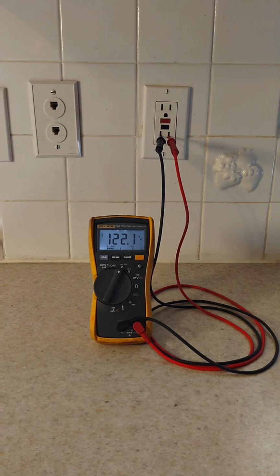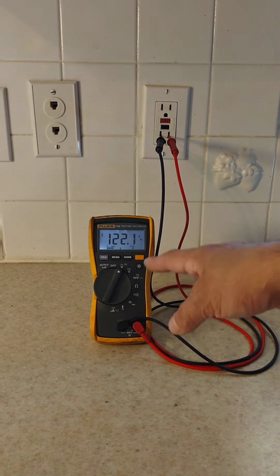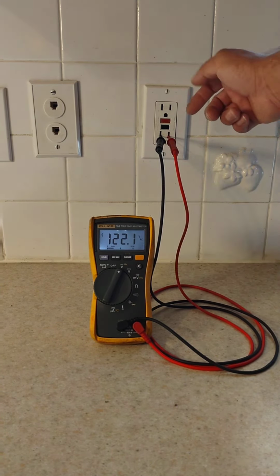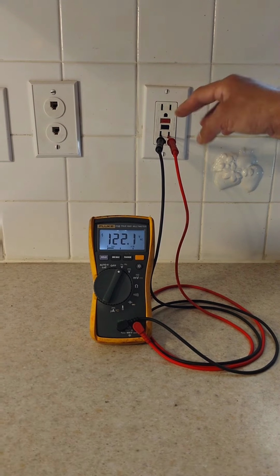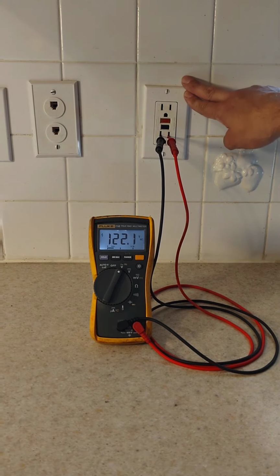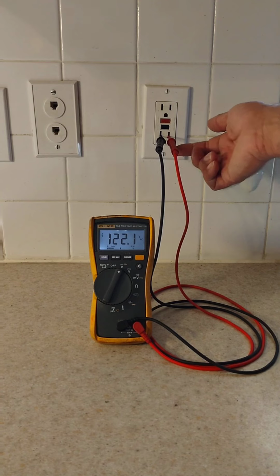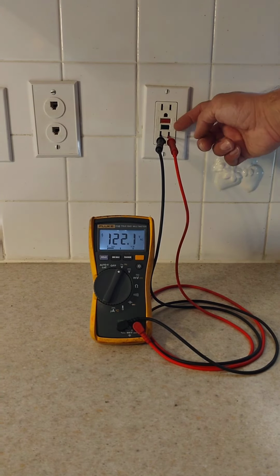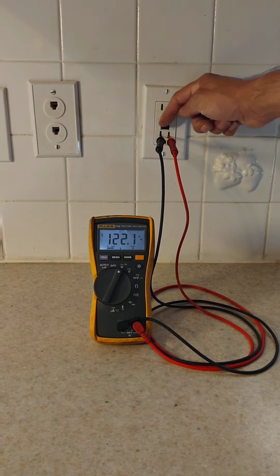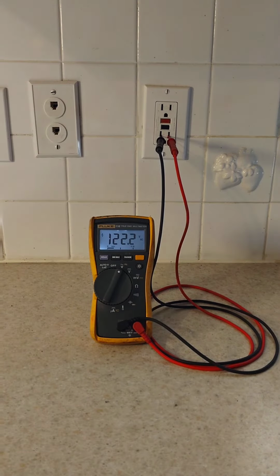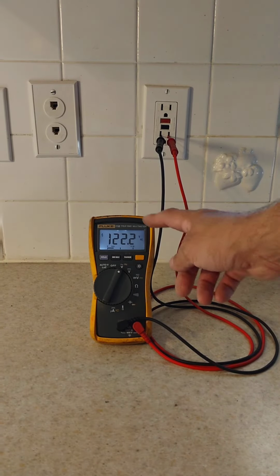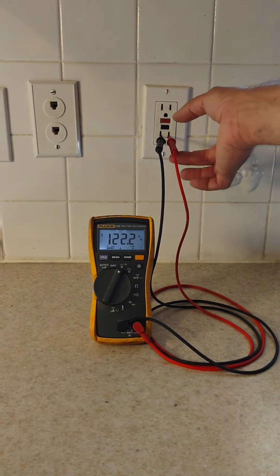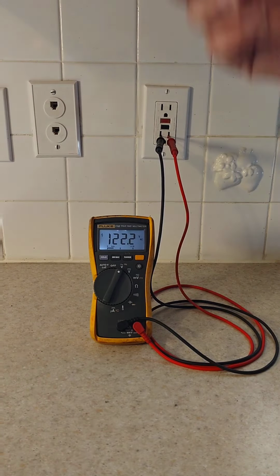So here's what I mean specifically. Right now, we're measuring 120 volts, open circuit, with no load, from a 120 volt outlet. I have my red probe in the line terminal, and I have my black probe in the neutral terminal. And the question I'm asking is, what is our meter going to display if I remove the probe from the neutral pin? Final chance. Make your guesses.